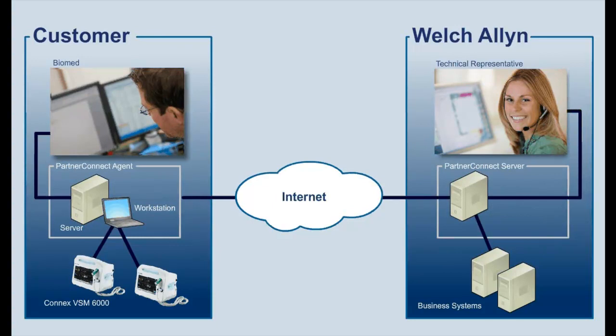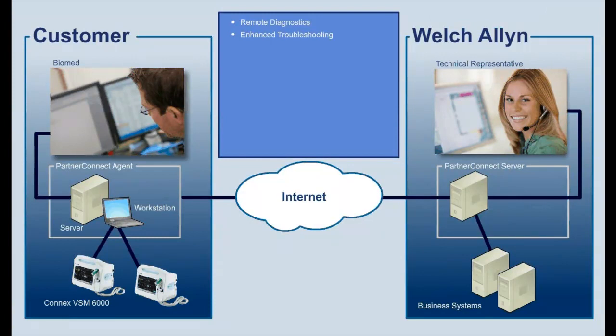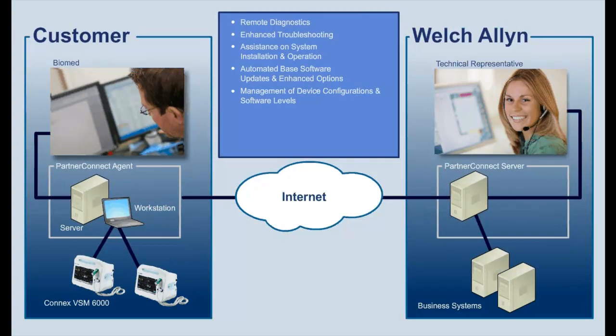The Welch Allyn Service Tool notifies you when there is an update available for a particular device. Upon connecting the device to the PC with an internet connection, the update can be installed. Partner Connect, interfaced with the Welch Allyn Service Tool, allows a Welch Allyn Technical Support Representative to provide remote diagnostics, enhanced troubleshooting, assistance on installation and system operation, automated base software updates and enhanced options, management of device configurations and software levels, device metrics, run time, as well as delivery of purchased software options and licenses.